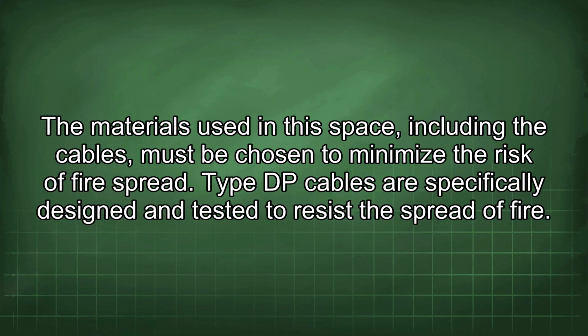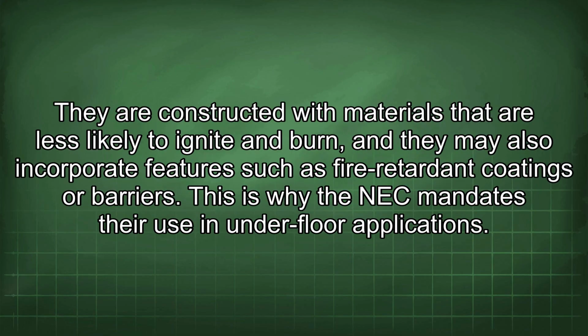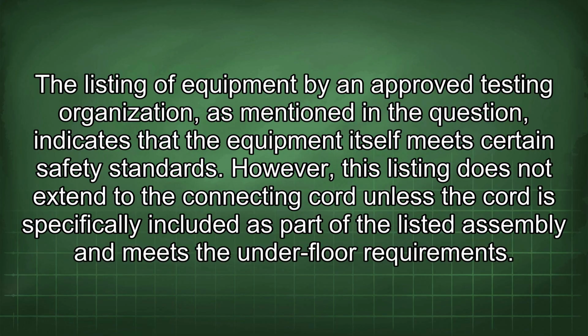Type DP cables are specifically designed and tested to resist the spread of fire. They are constructed with materials that are less likely to ignite and burn, and they may also incorporate features such as fire retardant coatings or barriers. This is why the NEC mandates their use in underfloor applications. The listing of equipment by an approved testing organization, as mentioned in the question, indicates that the equipment itself meets certain safety standards. However, this listing does not extend to the connecting cord unless the cord is specifically included as part of the listed assembly and meets the underfloor requirements.